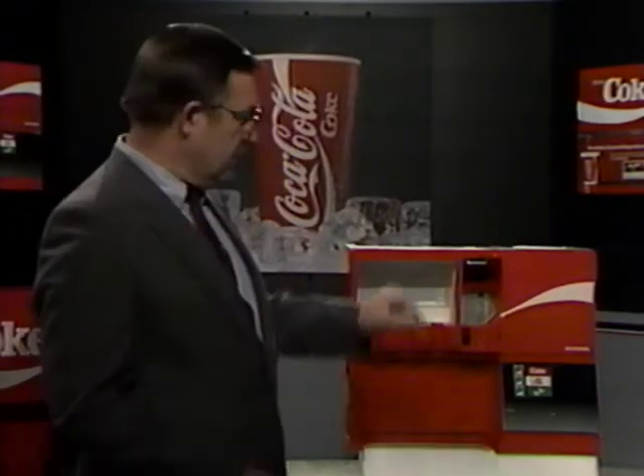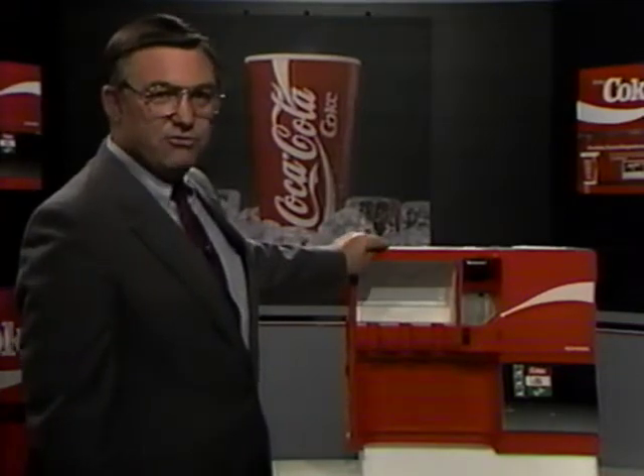At this point, remove the front panel so you can get to the sensor and dry it off. Now, we normally use compressed air or compressed CO2 to blow the sensor dry, and it's very sensitive and hard to dry off. If you turn the machine back on and the B light is still blinking, then look at the edge connector where the sensors connect to the ECM board and dry them off. Occasionally water will get on that and it'll act just like the sensor.